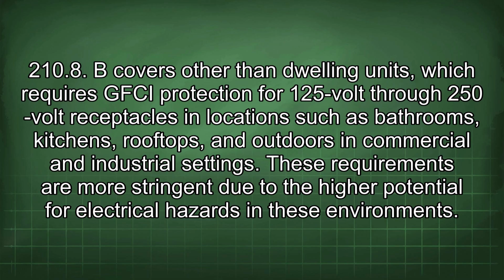210.8 B covers other than dwelling units, which requires GFCI protection for 125 volt through 250 volt receptacles in locations such as bathrooms, kitchens, rooftops, and outdoors in commercial and industrial settings. These requirements are more stringent due to the higher potential for electrical hazards in these environments.